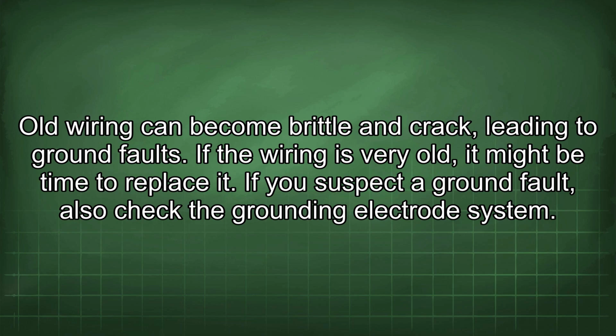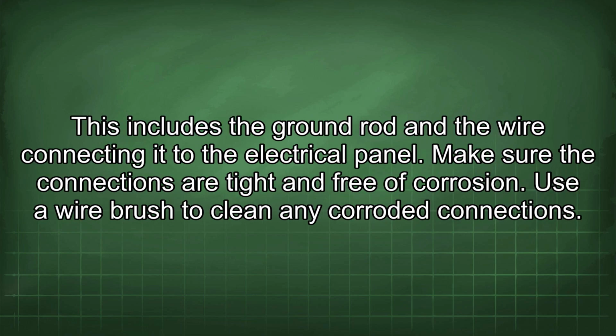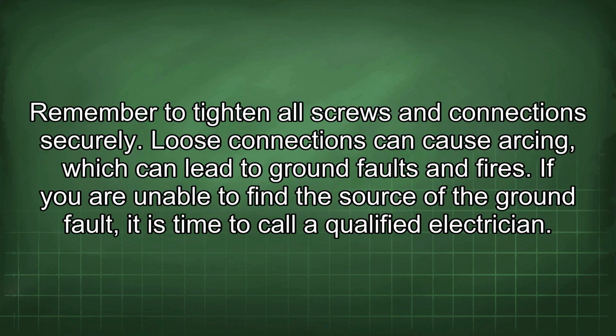If you suspect a ground fault, also check the grounding electrode system. This includes the ground rod and the wire connecting it to the electrical panel. Make sure the connections are tight and free of corrosion. Use a wire brush to clean any corroded connections. Remember to tighten all screws and connections securely. Loose connections can cause arcing, which can lead to ground faults and fires.